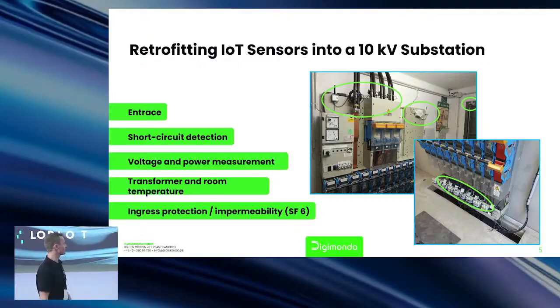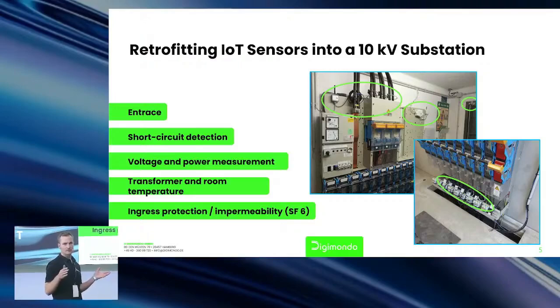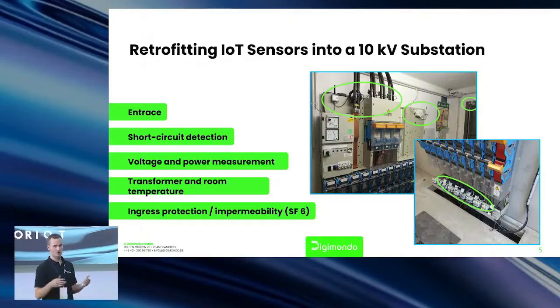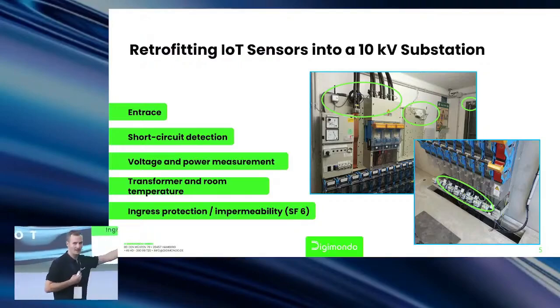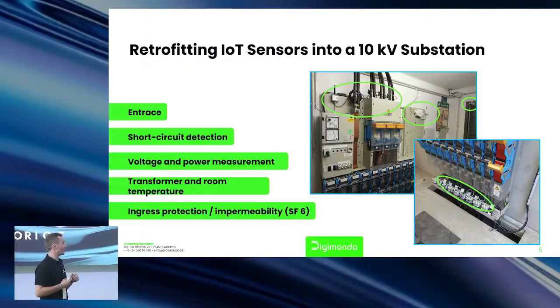We installed a couple of sensors, starting with 30 substations that our customer chose because those had the most problems. The first idea might be that they'd take substations that are far away, but no, they did the exact opposite. They equipped the first 30 substations that were quite nearby, because if there's an outage and they don't know where, they can directly identify the asset they have to drive to, saving time instead of taking a longer drive.